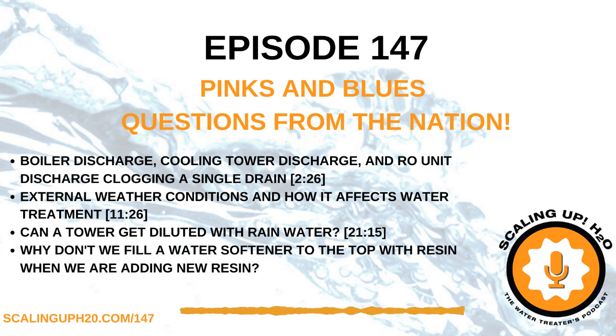So here's the warning, here's some math. The equation for evaporation is evaporation equals 0.001. Well, hey, that's 1 over 1,000. That's our 1 pound and 1,000 BTUs. That's where that number comes from. Times our recirculation rate. That's episode 128. Knock yourselves out. I talk all about that. Times our delta T, that's simply the temperature of the water coming in at the top of the tower versus at the bottom of the tower, times the sensible loss of heat in percentage. Now, it's that sensible loss of heat that we're going to address to answer Bernadette's question.